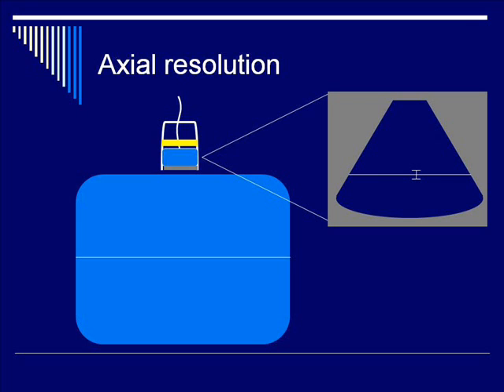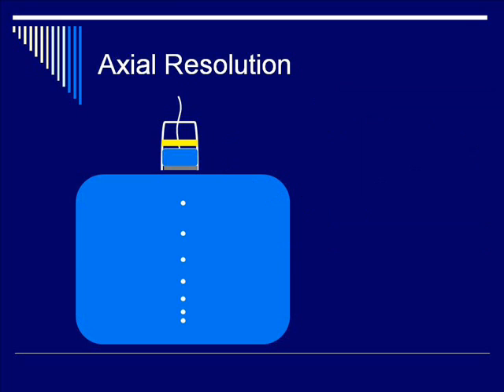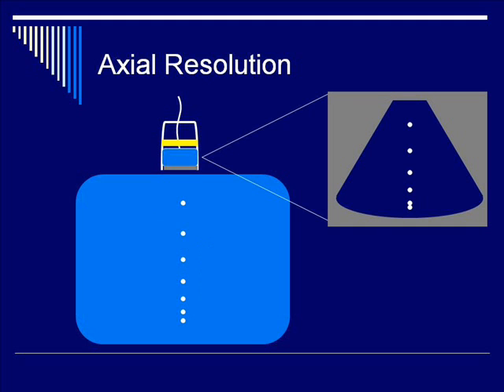Another way is to have successively closer, very small targets. For example, you could have two reflectors that are about two millimeters away, then two reflectors that are about a millimeter away, then one that's 0.75 millimeters away, then one which is 0.5 millimeters away, and so on. You then measure the distance between the two closest reflectors that you can resolve, and this is also going to be the axial resolution.